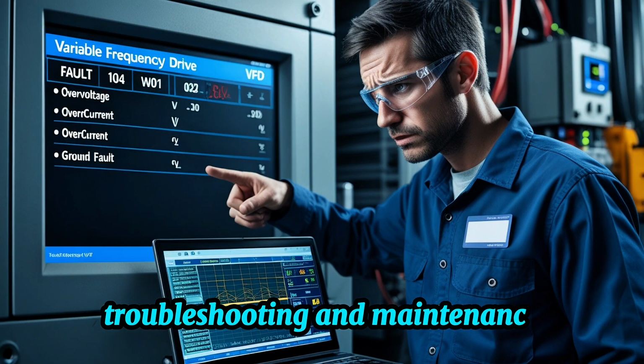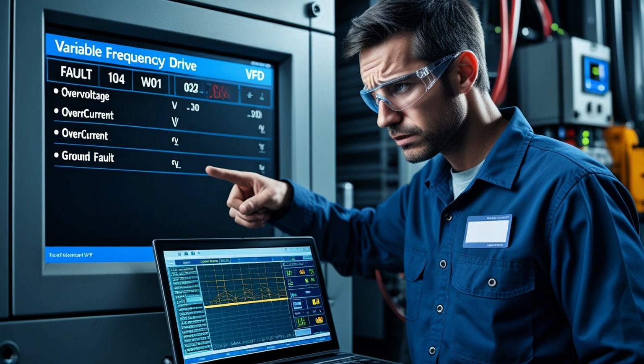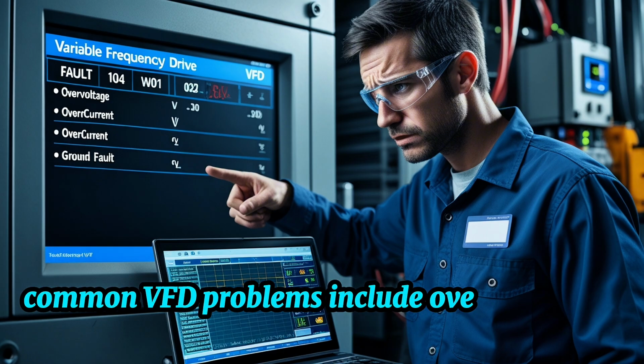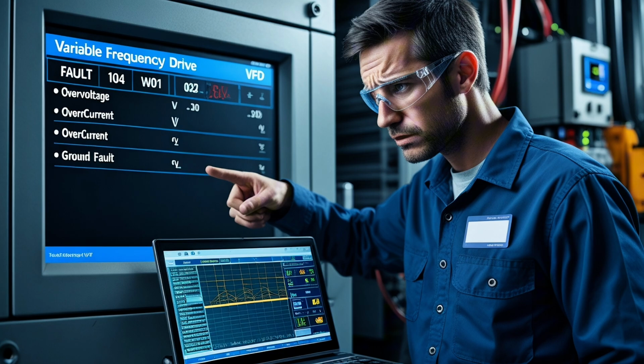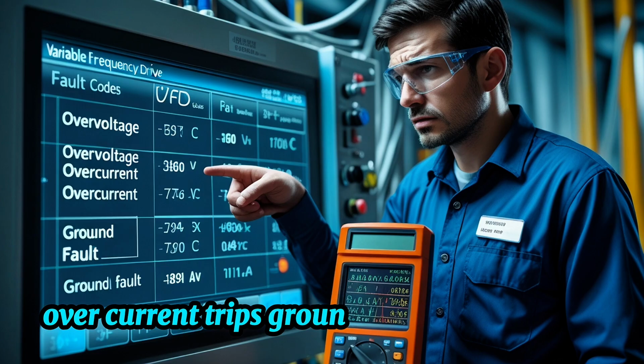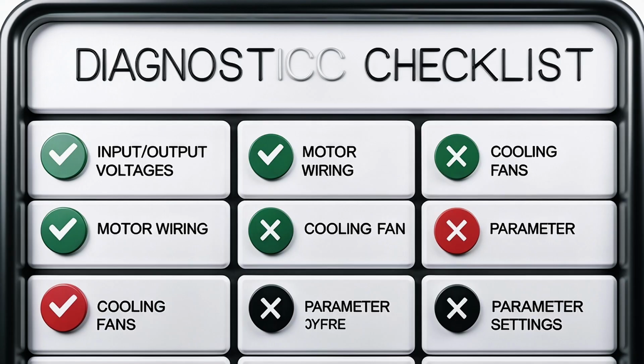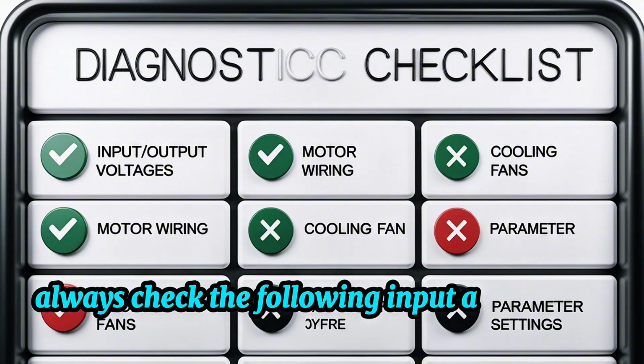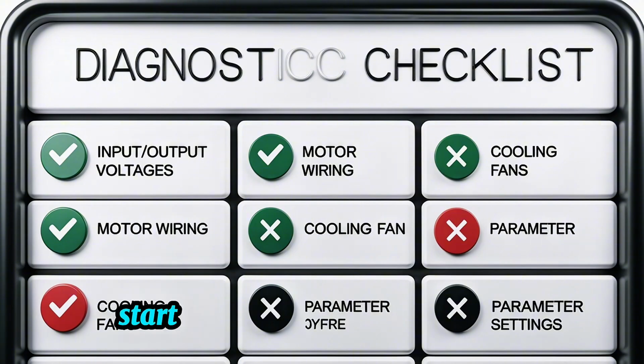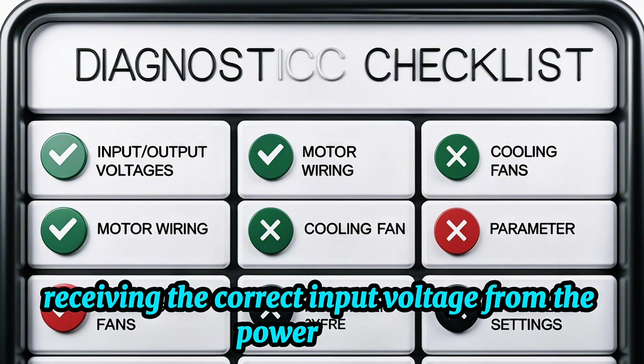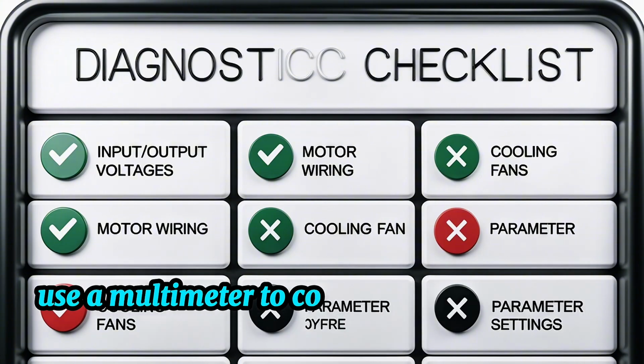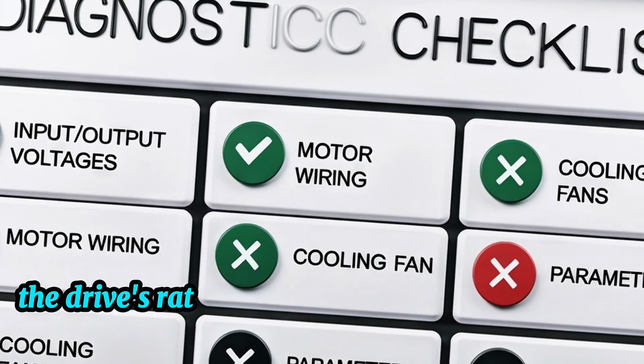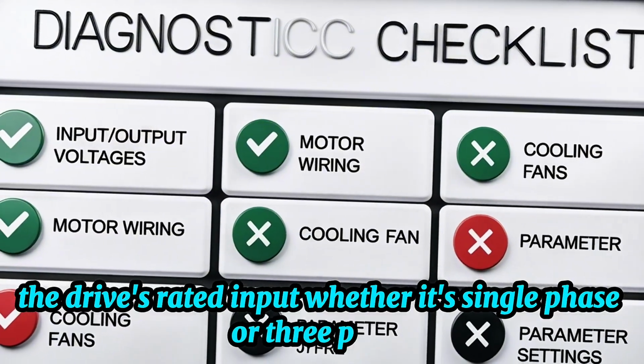Troubleshooting and maintenance. Even with the best equipment, issues can arise. Common VFD problems include overvoltage or undervoltage errors, overcurrent trips, ground faults, overheating. To troubleshoot a VFD, always check the following: input and output voltages. Start by verifying that the VFD is receiving the correct input voltage from the power supply. Use a multimeter to confirm that the voltage matches the drive's rated input, whether it's single-phase or three-phase.